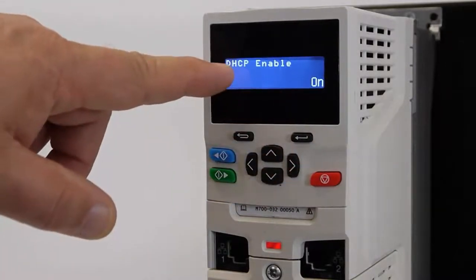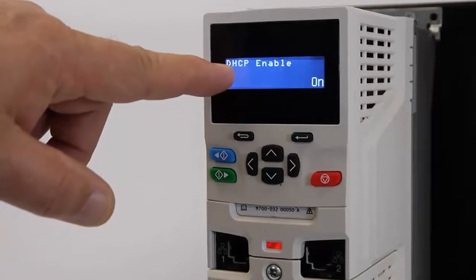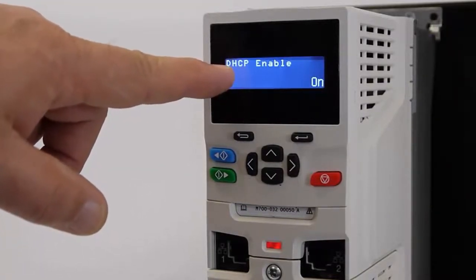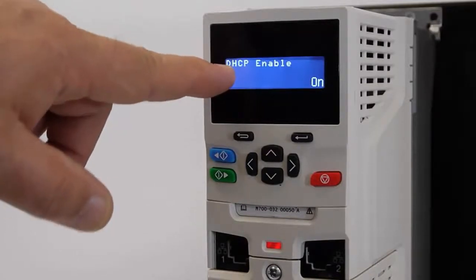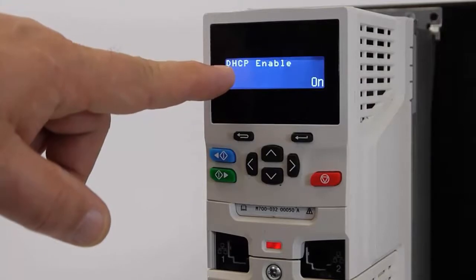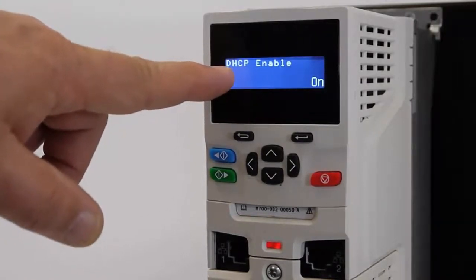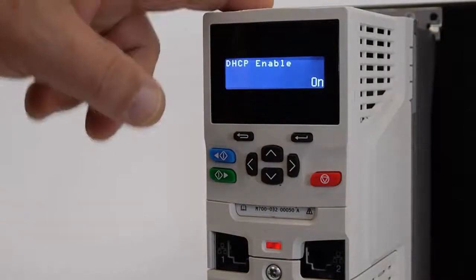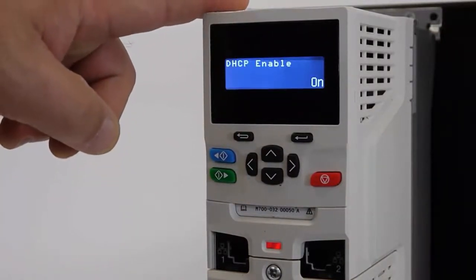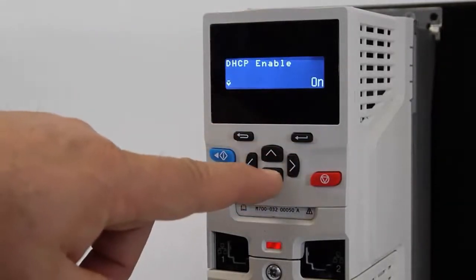This parameter is DHCP enable, which stands for Dynamic Host Control Protocol. If this Unidrive M700 were on a network that had a DHCP server available, it would use that server to obtain its IP address. However, there is no DHCP server here today, so I'm going to turn this off.